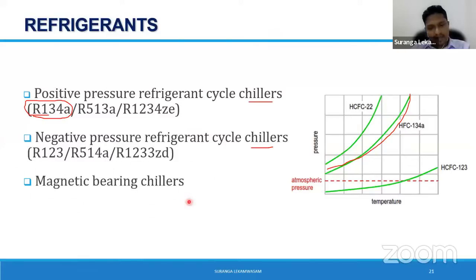But the magnetic bearing chillers obviously run on a positive pressure cycle, which uses R134A. Okay. When comparing positive pressure versus negative pressure, you can see the negative pressure centrifugal chillers are a little more efficient, right? A little more efficient than the positive pressure ones. One reason may be that their chiller lift is very low compared to positive pressure. If you compare R123 versus R134A, the R123 chiller lift is less. Therefore, they run at low RPM. You can eliminate the gear drives. That may be one reason why they are better in efficiency, and there may be many more reasons.